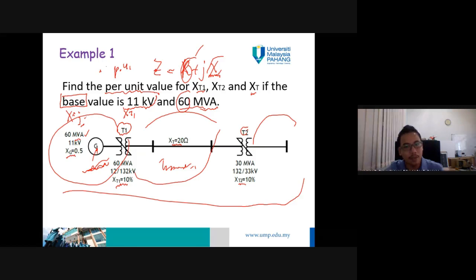This is the specific value for each component written in this single line diagram. For transformer one, they also give you MVA, but this transformer is apparently the step up transformer, because the voltage is step up. That's why the input, or the primary part, is 12 kilovolts, and the secondary part is 132, since this is the step up transformer.